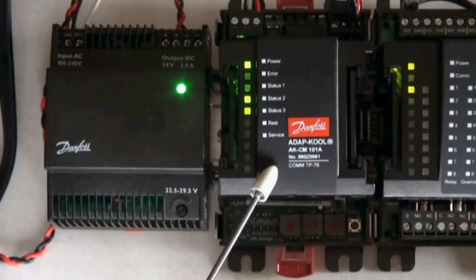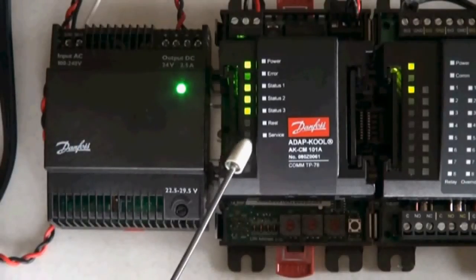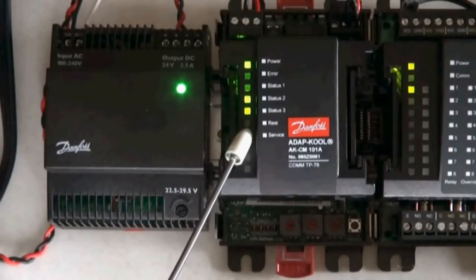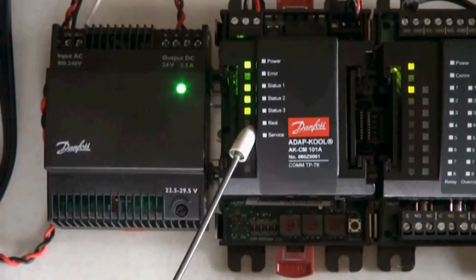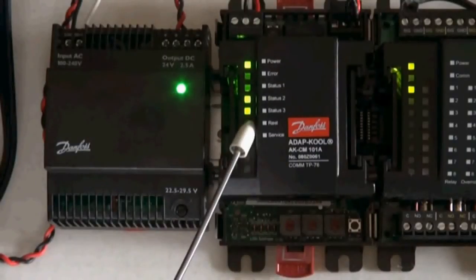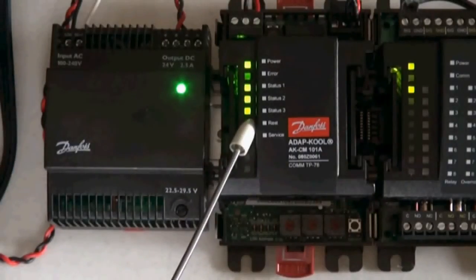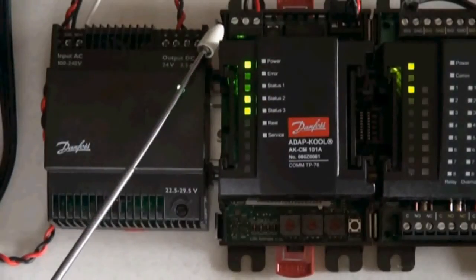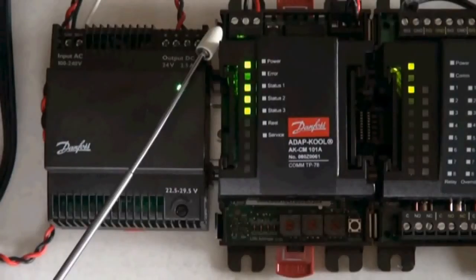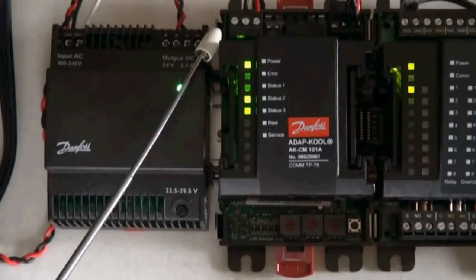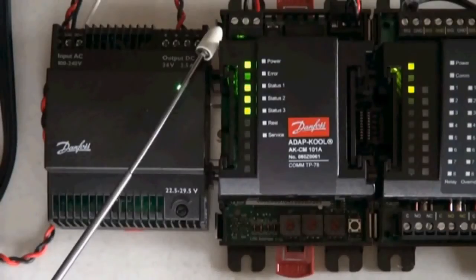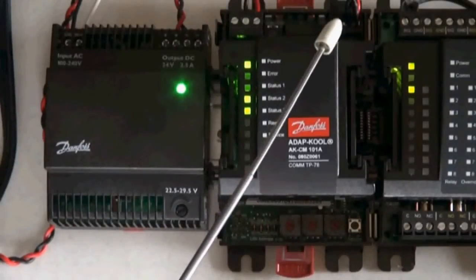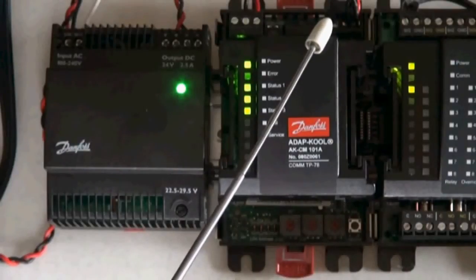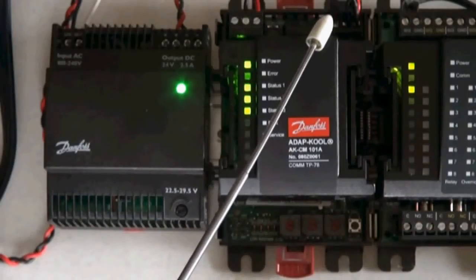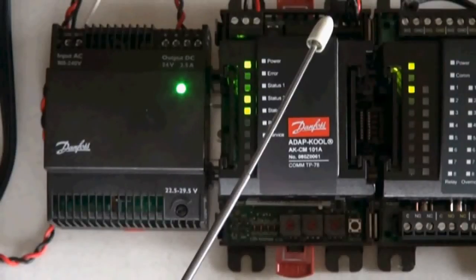Moving on to the communication module, you'll see the pattern of lights here indicates good communication. Status 1 should blink, status 2 and 3 should be on steady, along with the power light. At the top, we have the 24 volt connection. This module can be powered with either 24 volts AC or DC. The other connector is for I/O communication back to the Danfoss 255. Note the location of the termination resistor, since this module is the end of the I/O loop.